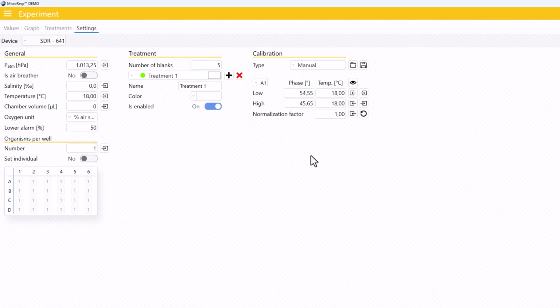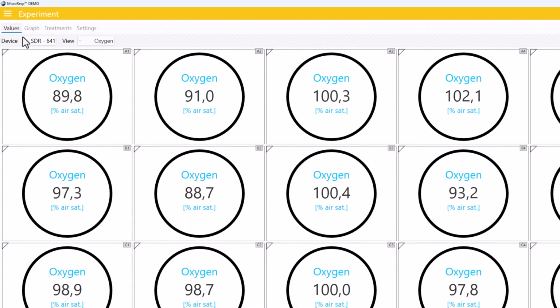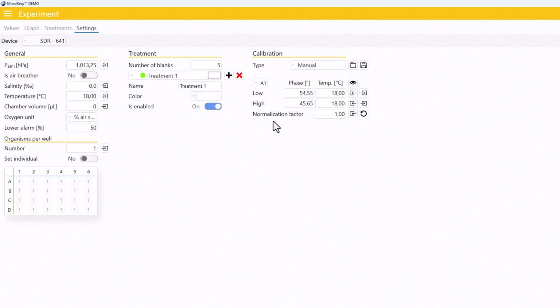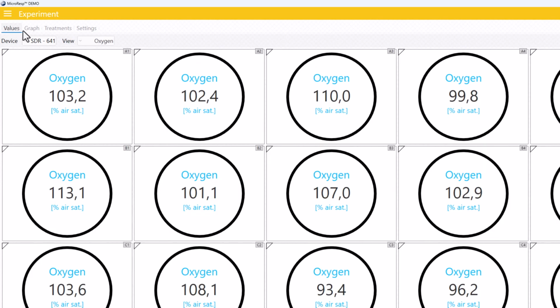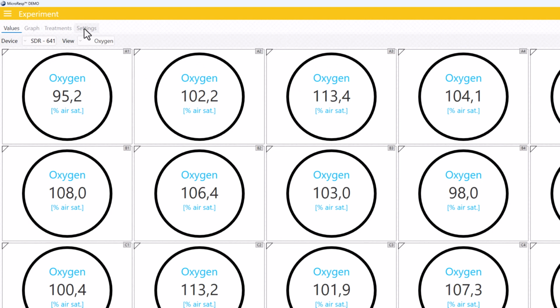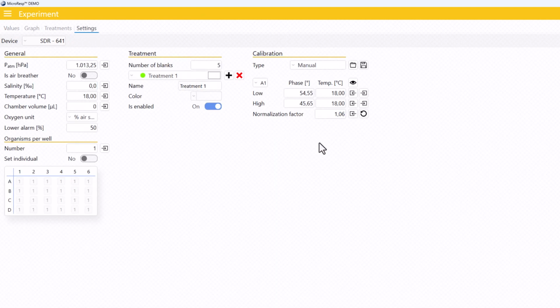In the calibration section, we find the normalization factor. Normalization will set all air saturation values to 100% by multiplying with a factor, so that each oxygen curve has the same starting point. If the oxygen sensor calibration is good, normalizing will not change the percent air saturation values much, typically less than plus minus 10% if performed at 100% air saturation. Normalization should be performed after setting both calibration points and when there's 100% air saturation, water or air in the wells.